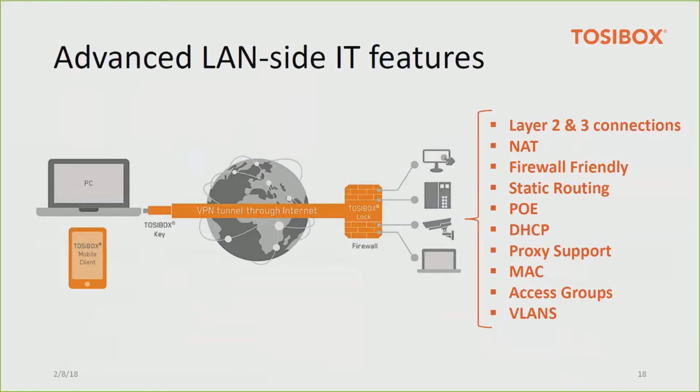Okay, so I'm putting this VPN device on their network, and their users are getting onto the devices. I think that's where you would go in through the second port. Yeah, you could use the secondary port on the JACEs and go in that way. That's the way we've had the lock set up in our building before: the primary port plugged into our building network so that everyone here locally can get to it, and the secondary port plugged into the lock so that remotely we could get to it. Okay, so in that case, I would have to build my own network between my JACEs, my secondary port network. Correct, if you went that way. Or you'd have to get 3 locks, where their whole network is on the LAN side, which you don't want to do.